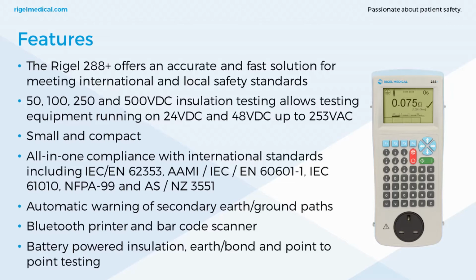Okay, so some of the key features of the Rigel 288. It offers an accurate and fast solution for meeting international and local safety standards. 50, 100, 250 and 500 volt DC insulation testing allows testing equipment running on 24 volt DC and 48 volt DC up to 253 volt AC. So we've got these lower insulation test outputs available for the 288, and this is to cover some of the safety extra low voltage devices that require insulation tests. You'll find that your traditional electrical safety analyzers only have the 500 and sometimes 250 volt DC. And this covers the ranges down to the safety extra low voltage, or class 3 as it's known in some standards.